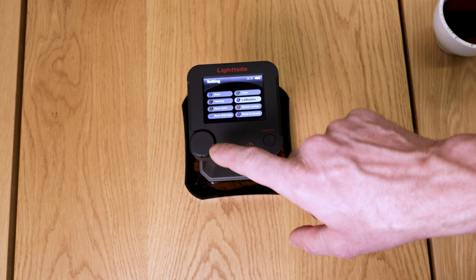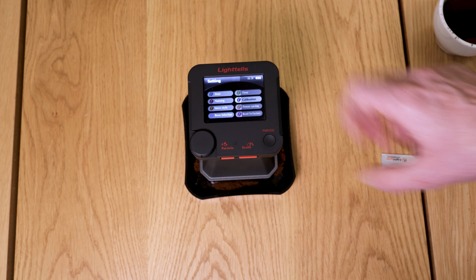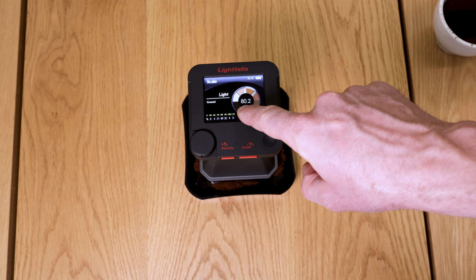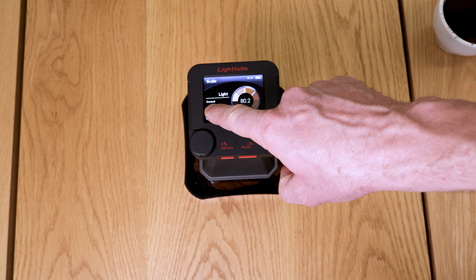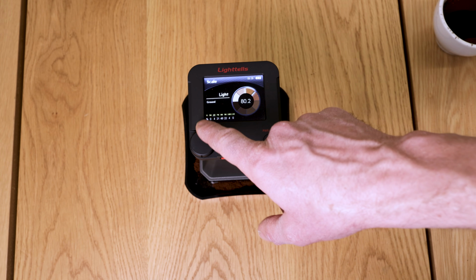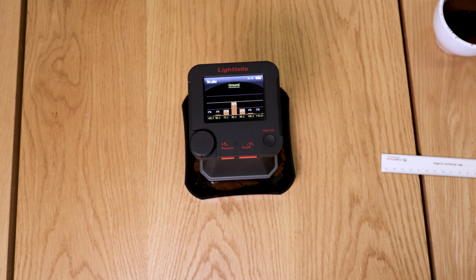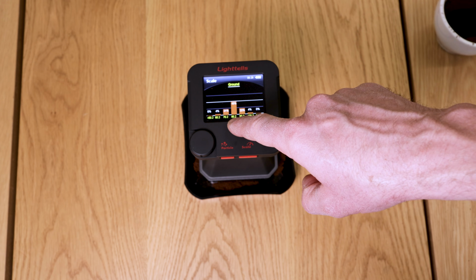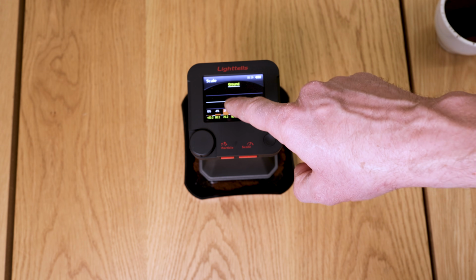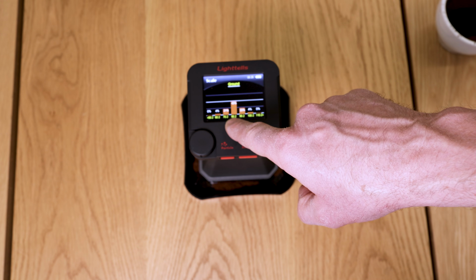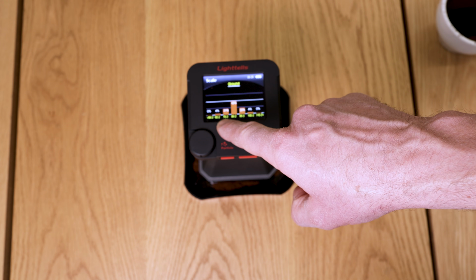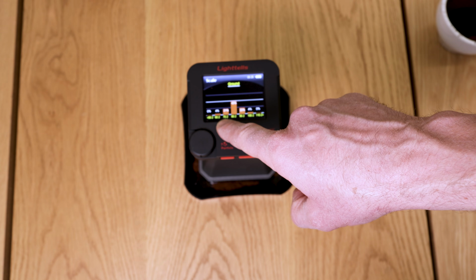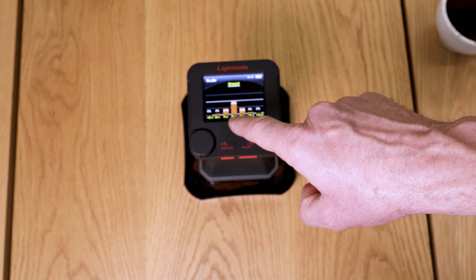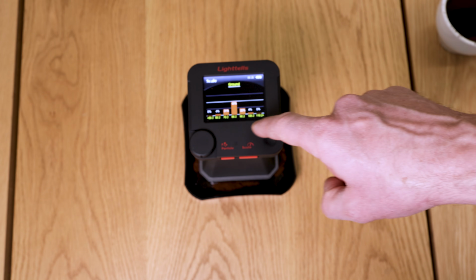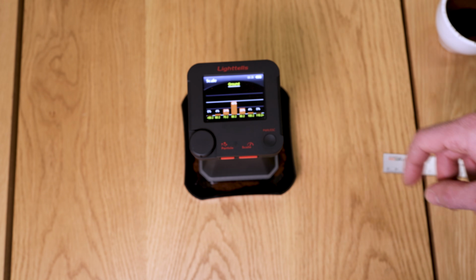Now I can just press particle, which is particle size analysis, or scale. So I'm doing the scale. And you see I again have here a color of 80.2. It discovered that I have ground coffee. And here are some values, but this is nicer displayed if I just press on this button. And then I see the distribution of the color values. So most of 49% is here in this range of 80.2 plus minus 5. And then here 21 in the range, which is a little bit lighter, 10 are a bit darker, then 22 in the range which is a bit lighter, so I can see the distribution, and it's actually quite even here in this sample. I do another measurement.